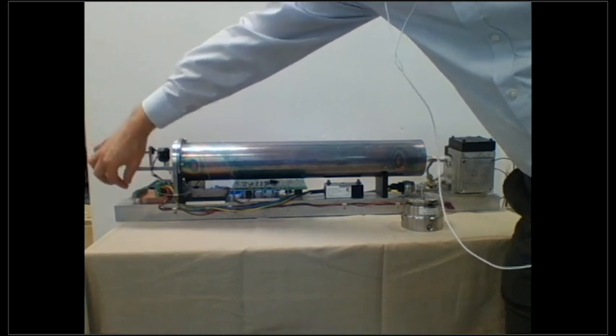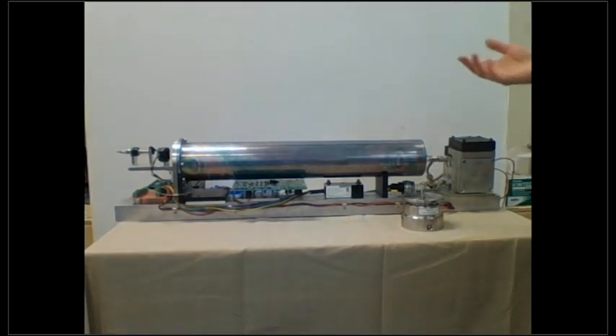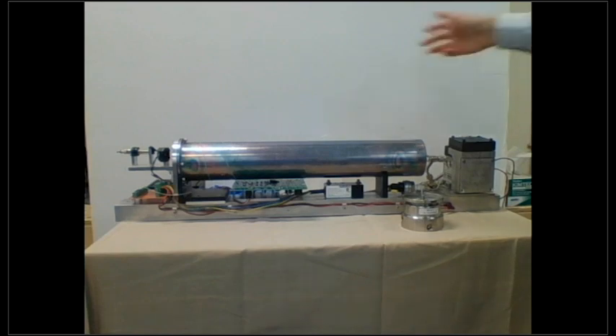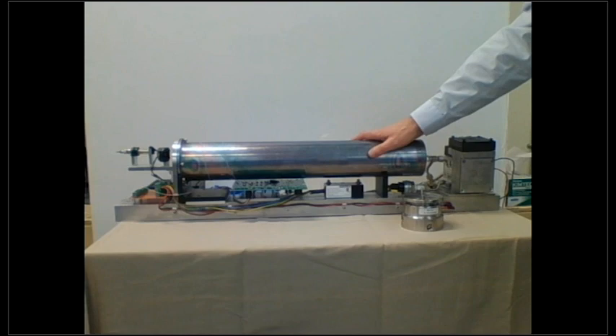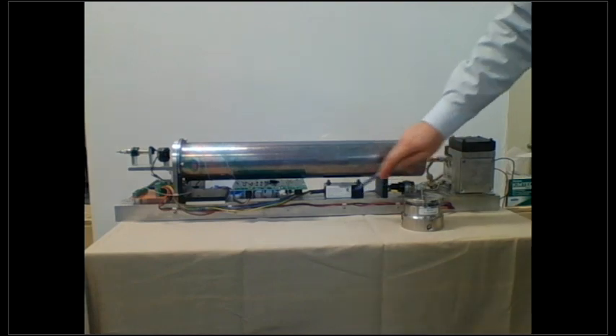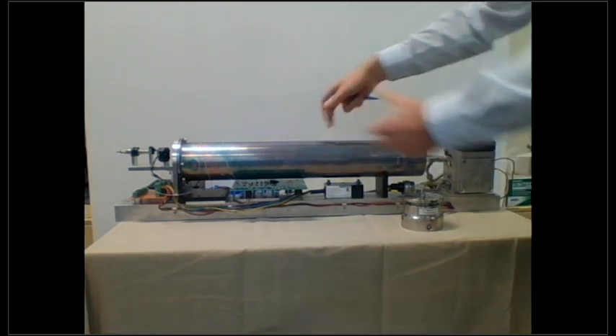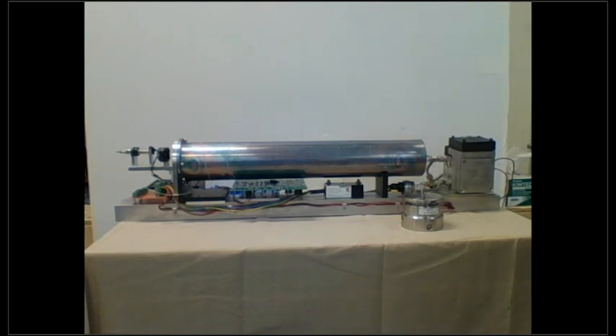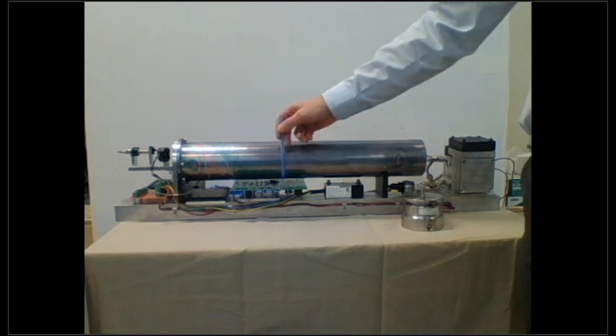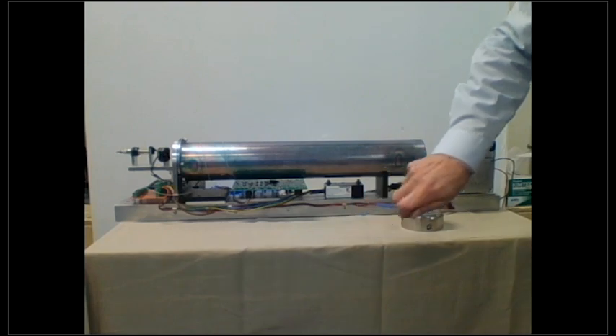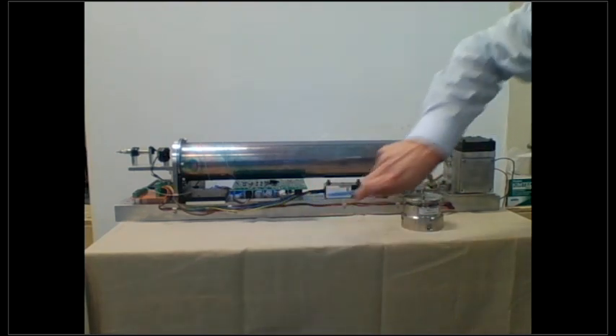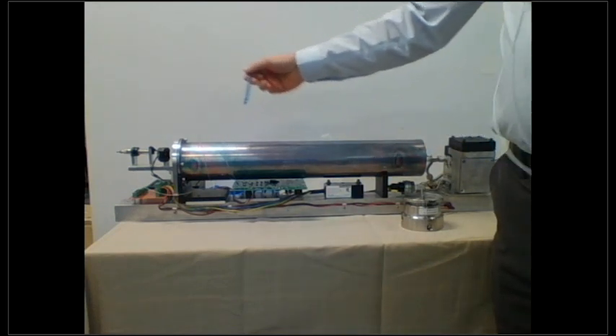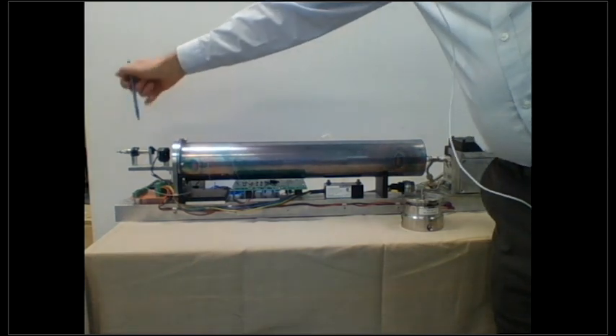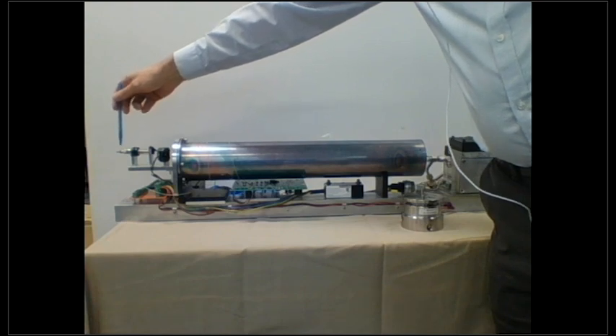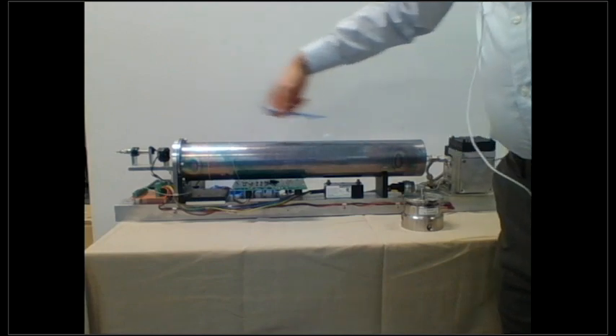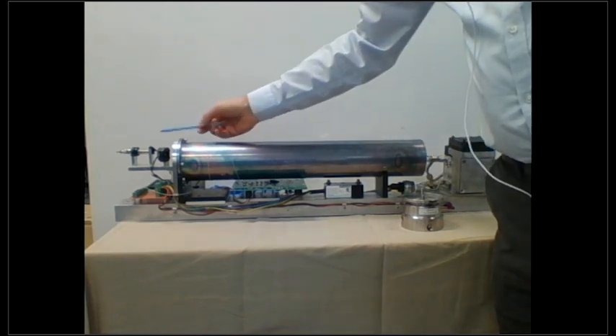If you're working with a Div 2 unit, you do have similar access to this, but it's not all on one piece. So you would remove the cell separately and remove the vacuum pump separately, but you do have full access to those components. So on the rail, we have a heater that's basically a contact heater. It just heats everything that's in contact with it. Gives a nice stable thermal environment for the optics. We have the laser driver board here. This basically generates the laser signal. So the laser itself is actually attached to this board on the bottom side. It's a fiberized connector. So you see this fiber optic cable here carries the laser output into the laser launcher, launches into the cell, goes through its 100 bounces, eventually pops back out, lands on this little mirror, and then hits the detector. And if your gas of interest is in the cell, of course, you get some absorbance and it makes a measurement.